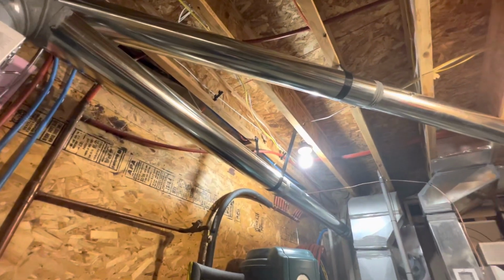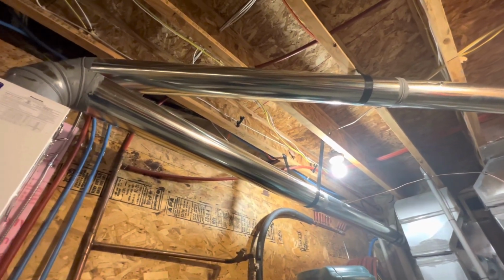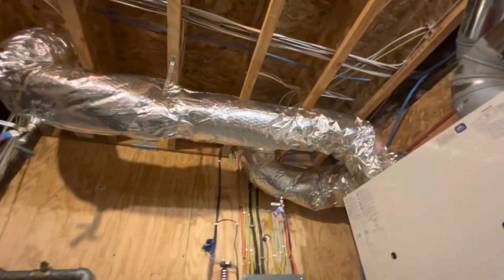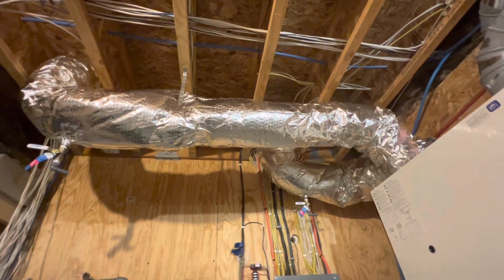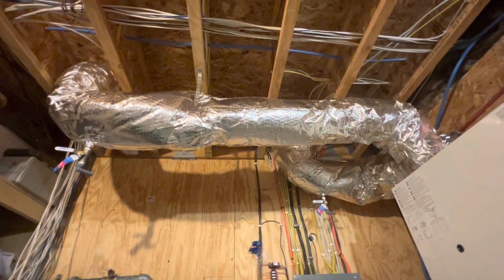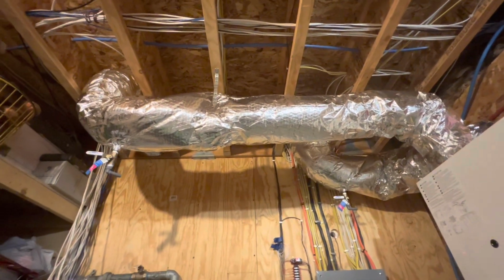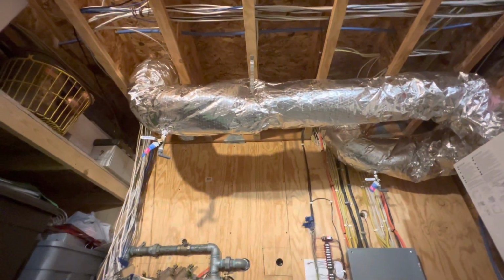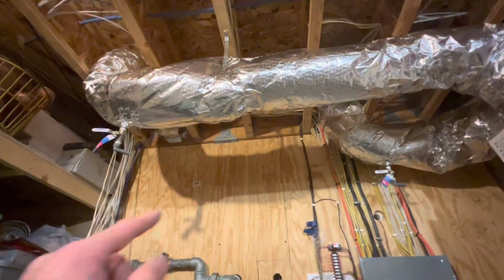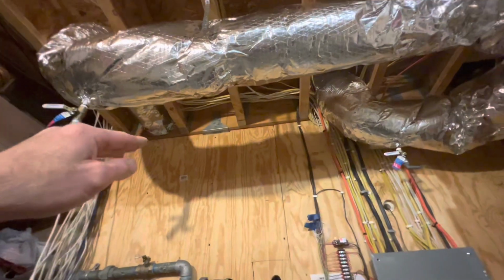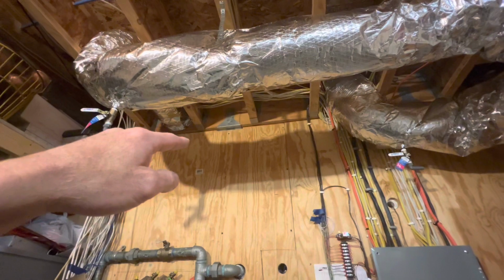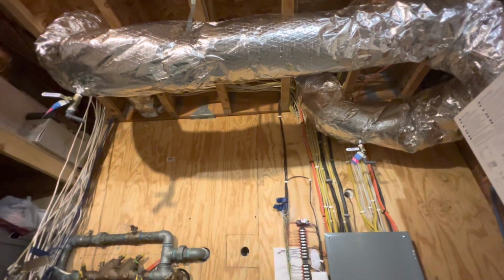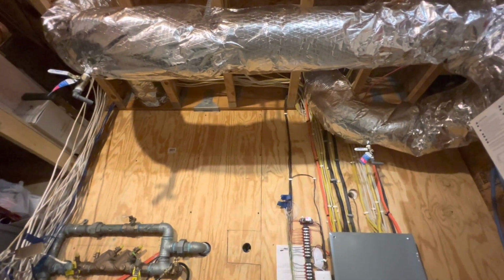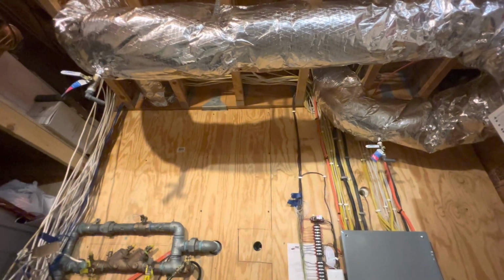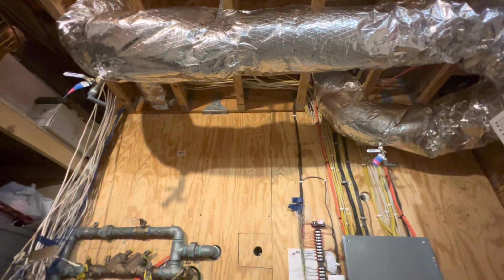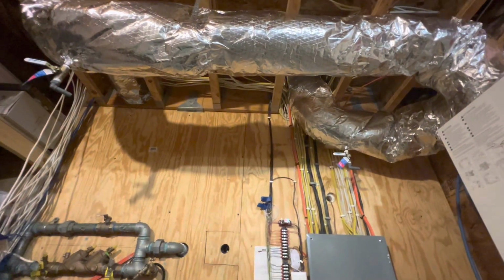Like I said, for my warm side ductwork, I used standard galvanized 6-inch ductwork. For my cold side, I used green 6-inch drain, waste, and vent PVC pipe. I wanted that because on the outside of the house, it has to go vertical up to the eave. The rim joist on my house is right at ground level, so if I would have just poked them out and put my vents there, it would have been sucking dirt or air right off the ground level outside. I wanted to get it up. I think the manual even calls for it to be 6 feet off the ground, so I took it up 9 feet off the ground to the eave line of the house, so I can make sure I get good fresh air, and don't get lawnmower exhaust or anything else.